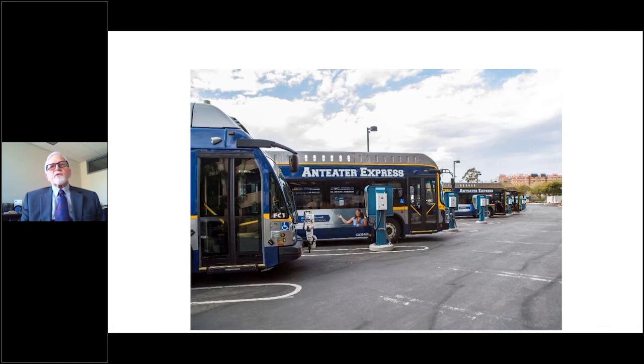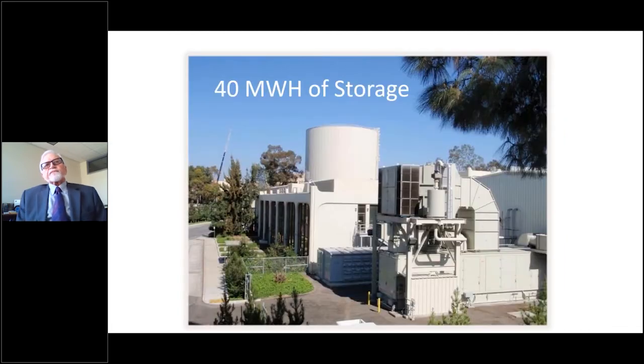There's another load management tool that actually works: that big thermal storage tank you see over by the central plant, holding 4.5 million gallons of chilled water, chilled to 38 degrees. The amount of energy it takes to chill that water for the whole tank is 40 megawatt hours. If that were a battery, it would be one of the hugest batteries in California. It makes a lot of sense to use your storage medium as a thermal medium if that's the end use.